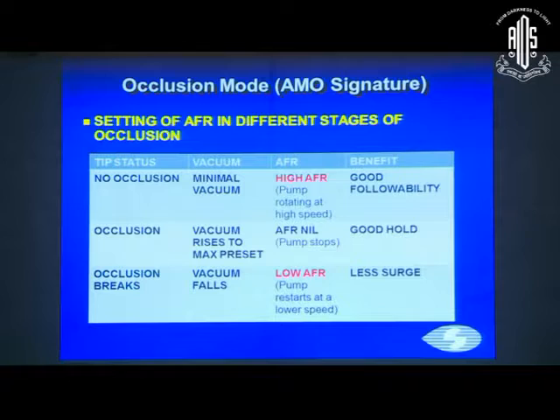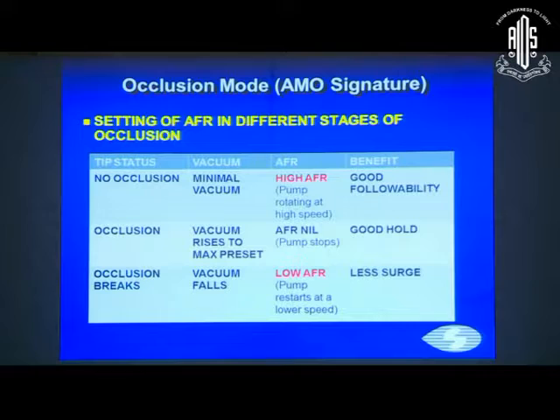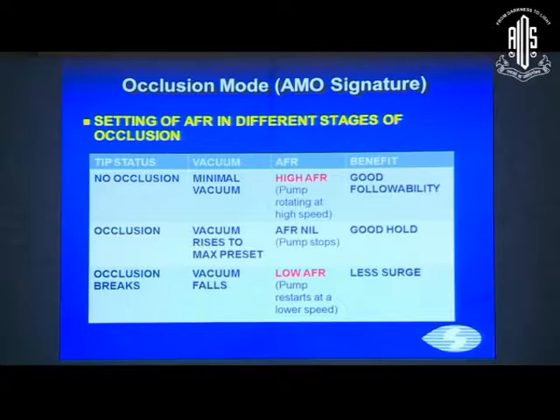When occlusion occurs, the vacuum rises to a maximum preset and the aspiration flow rate becomes nil because the tip is occluded — the pump stops, giving a good hold. When occlusion breaks, the vacuum falls, but a lower aspiration flow rate is set because different AFRs can be programmed for different stages of surgery. The pump restarts at the lower AFR, resulting in less surge.